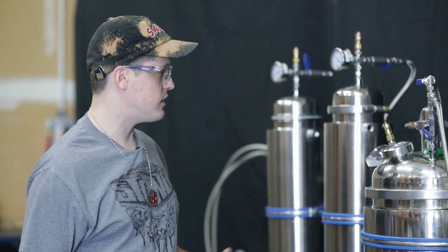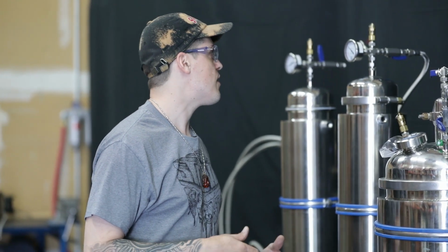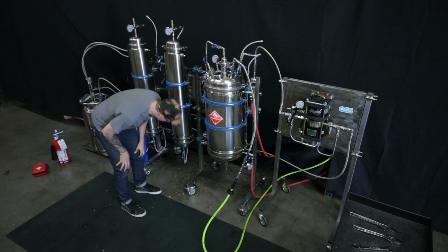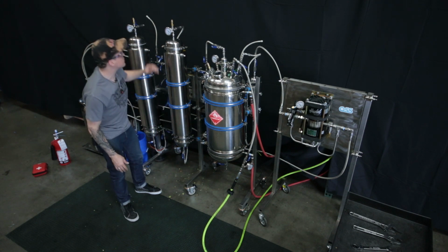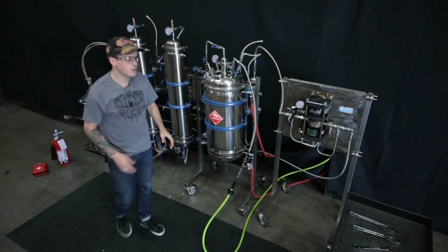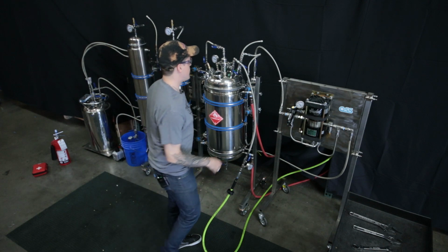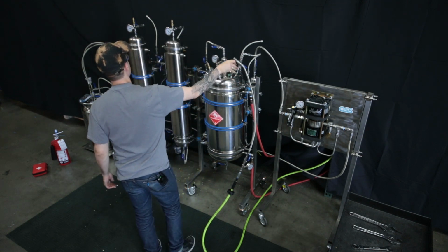So we're going to check for leaks in stages here. We're at 30 psi. We're just going to listen for any hissing, any leaks around the gaskets that we just connected. I don't hear anything. I'm also looking at my gauges, of course, and there's no movement. So it looks like it's safe to continue on. We'll go up.